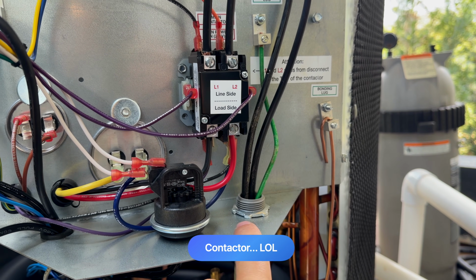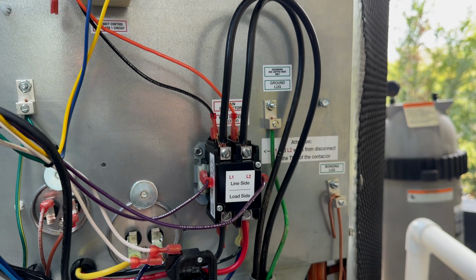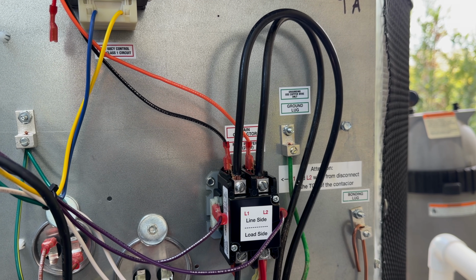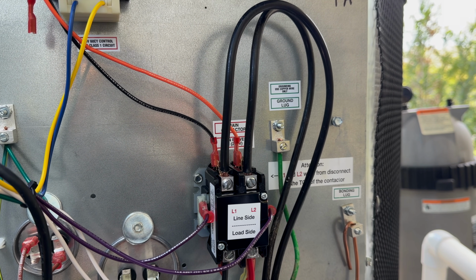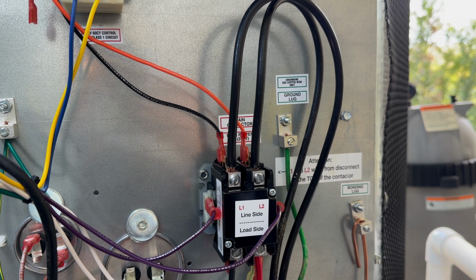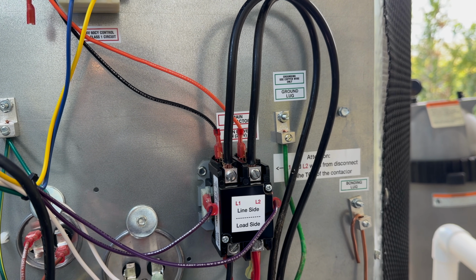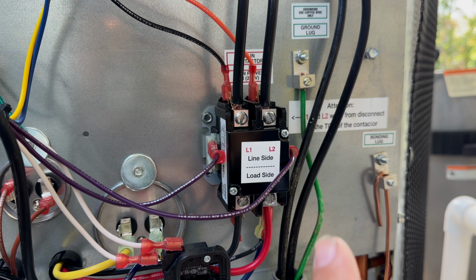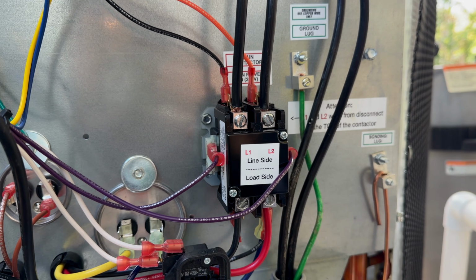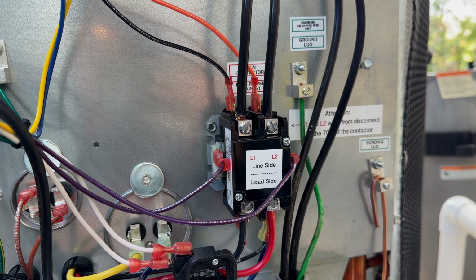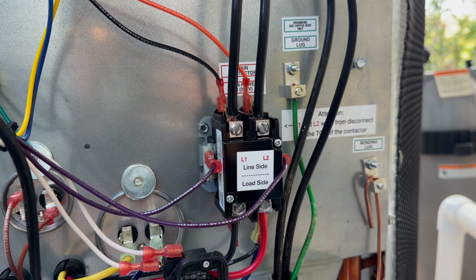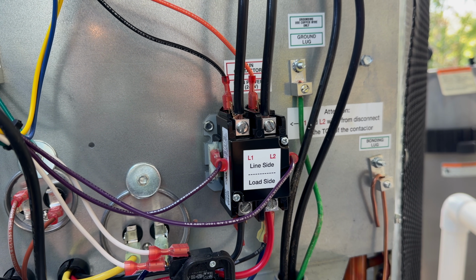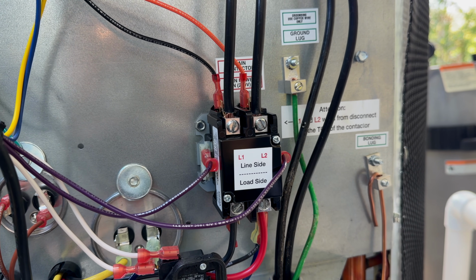And we have a 50 amp breaker, so these are number 8s. You can see I left ample room here for the next person after me, if they need to cut and make a new connection, there's plenty of wire there instead of having to rerun all the wiring. You see there's a little copper exposed - I do that simply just to make sure that there's no insulation underneath that lug to give a bad connection or inconsistent power, so on and so forth.